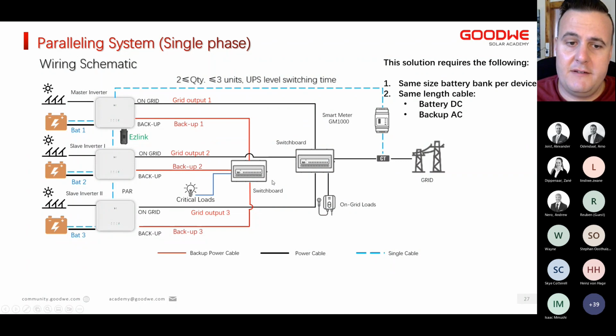What we have to keep in mind in this configuration is the same size battery bank per inverter, and try and keep the battery cables as well as the backup AC cables more or less the same length, just to make sure there is no discrepancy in resistance. And you'll see the master inverter gets the smart meter, and the rest only connect to one another.